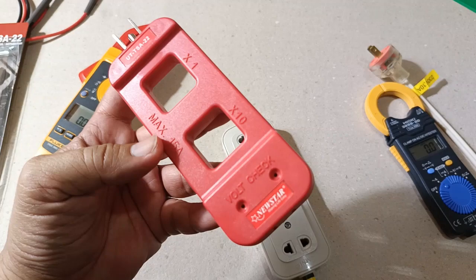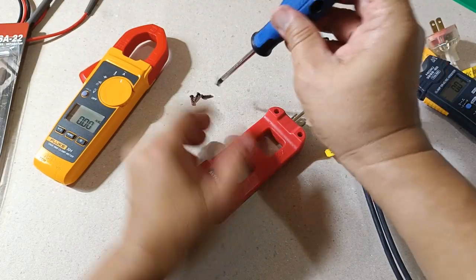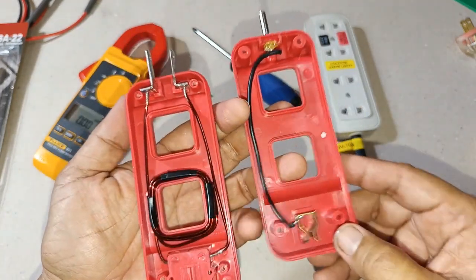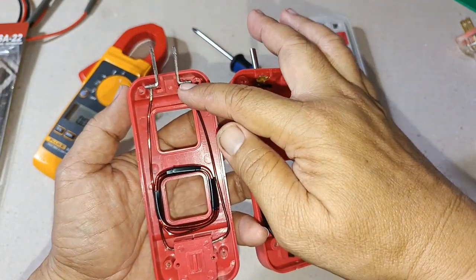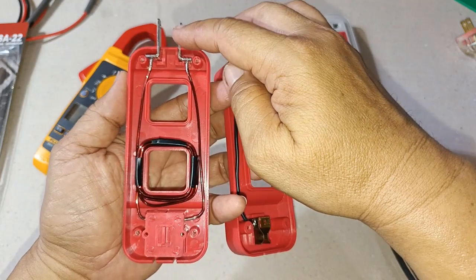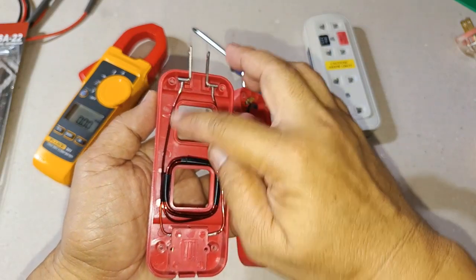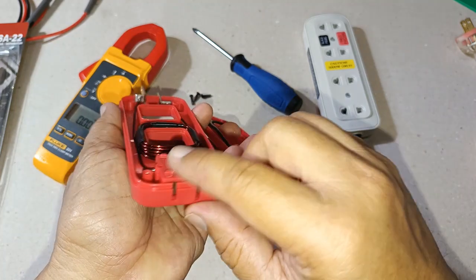So what exactly is meant by x1 and x10? To answer that question, we need to open this AC line splitter. This is the inside of the Newstar AC line splitter — the construction is quite simple. We can immediately see that this terminal post here represents the equipment grounding connection, and this could be line one and line two. As you can see, line one goes from this terminal location all the way straight to the terminal point here where the load is connected, while line two passes through this part and, when it reaches this hole, is wound 10 times before going to its final terminal point.